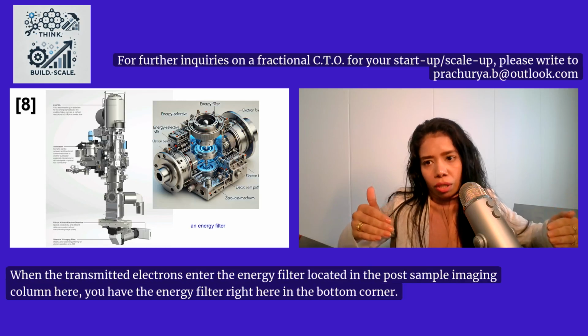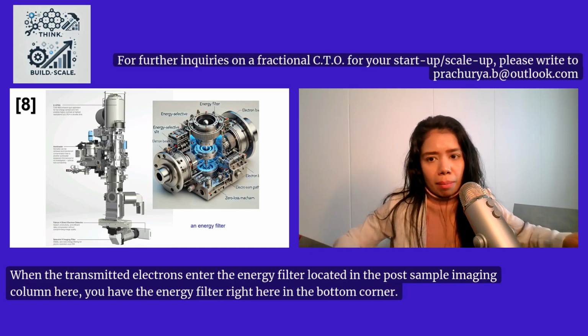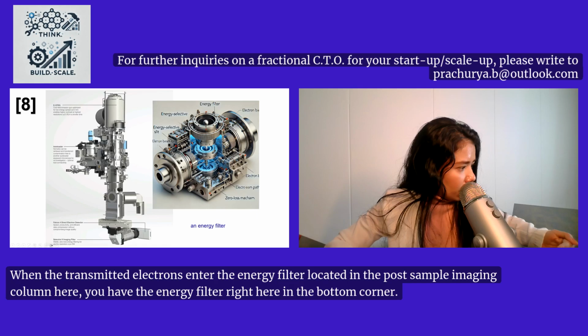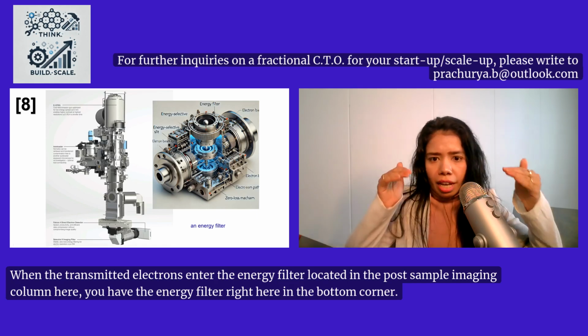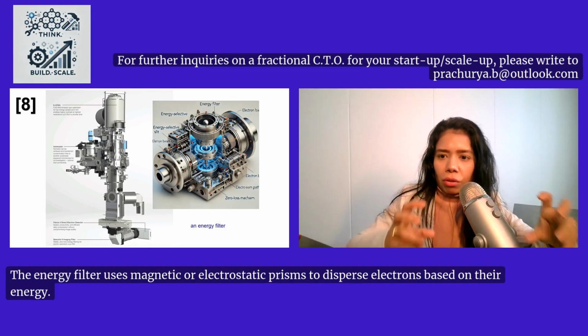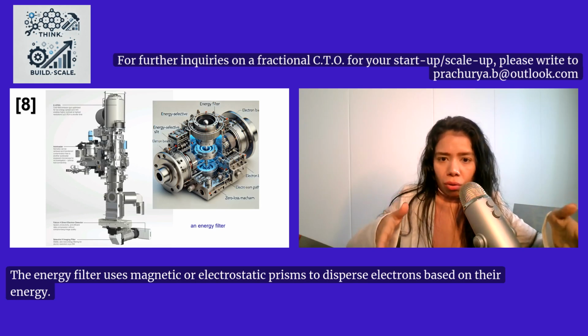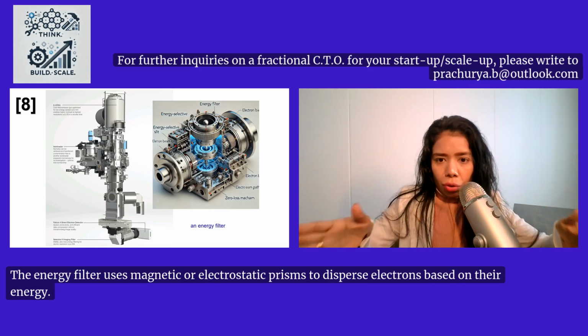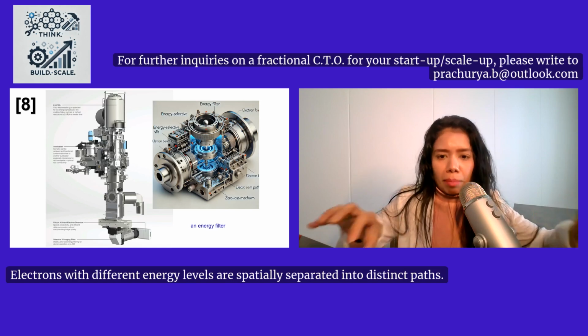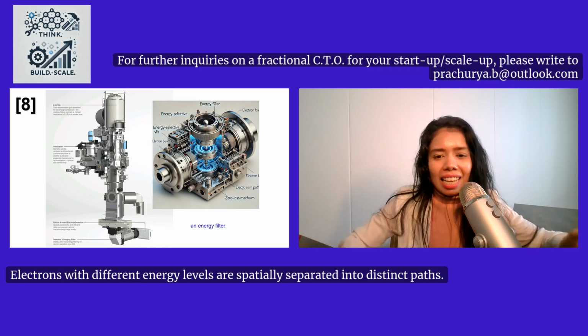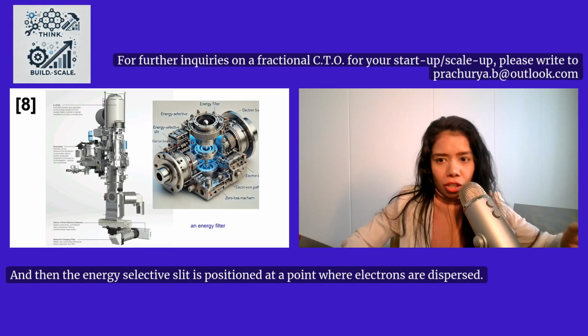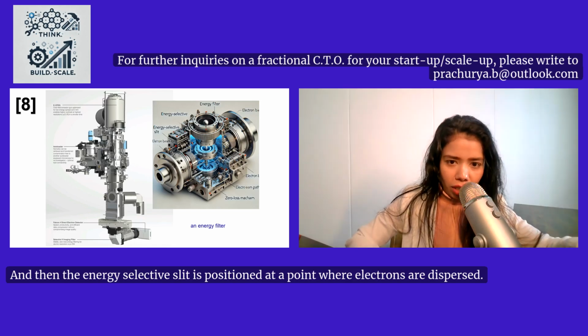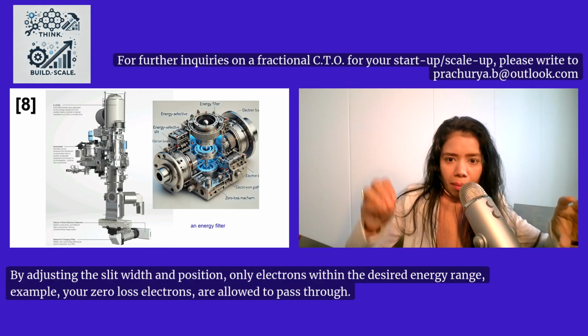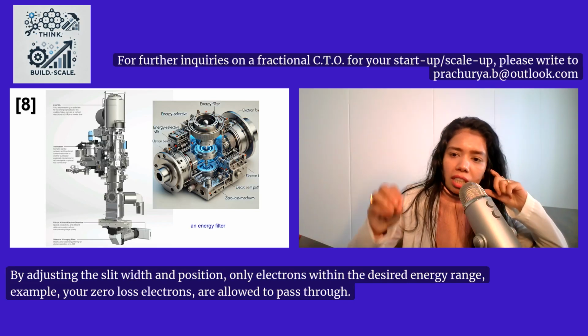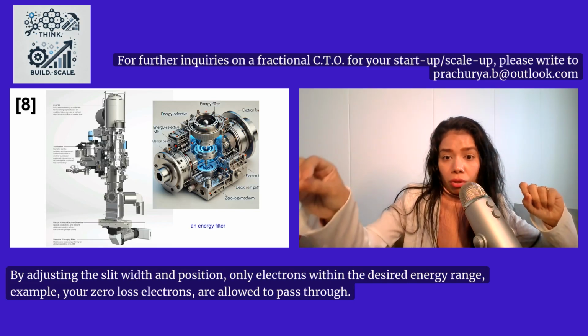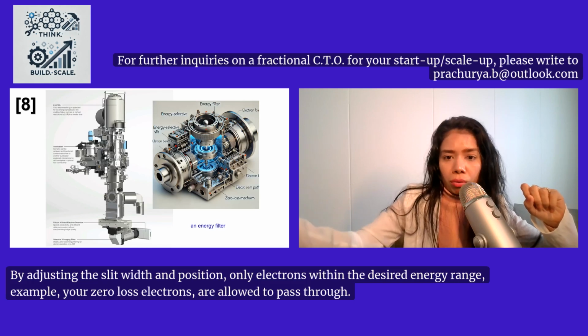When the transmitted electrons enter the energy filter located in the post-sample imaging column, here you have the energy filter right here in the bottom corner. The energy filter uses magnetic or electrostatic prisms to disperse electrons based on their energy. Electrons with different energy levels are spatially separated into distinct paths. And then the energy selective slit is positioned at a point where electrons are dispersed. By adjusting the slit width and position, only electrons within the desired energy range, for example your zero loss electrons, are allowed to pass through.